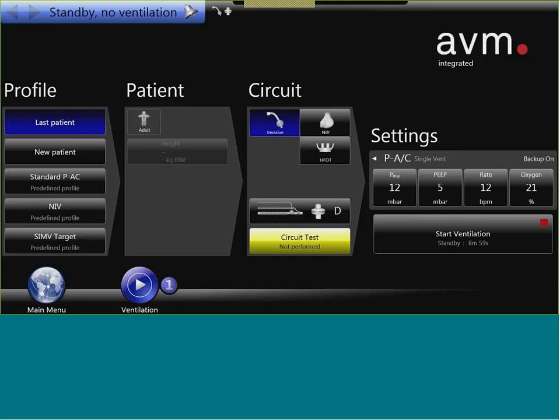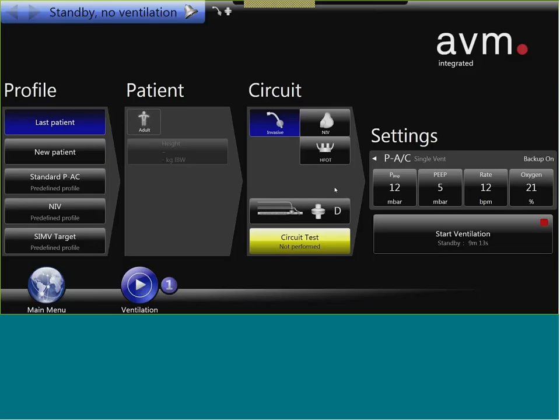The next question is, what do I do with the expiratory side? Technically, it's not necessary to have a filter at the expiratory side for Bellavista. So there is no way that Bellavista would need a filter there. There are ventilators out there which have an expiratory filter, and this makes sense, especially nowadays, because you don't want to disperse viral load from one patient to another.